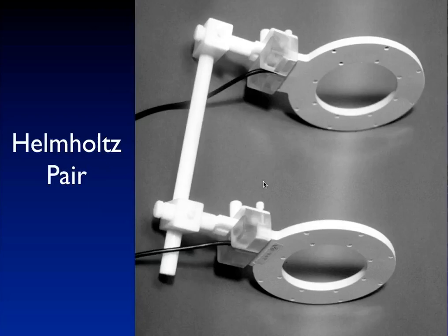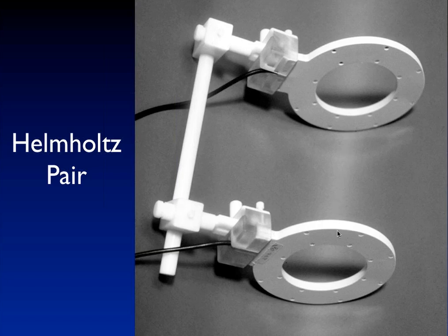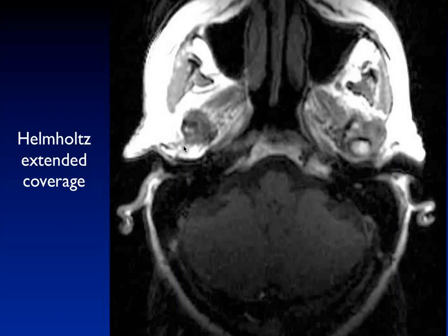A Helmholtz pair consists of two parallel loop coils. As described, you get more uniform signal intensity in the middle when they're spaced at about 1.3 times the radius of the coil. For many years this configuration was used for TMJ imaging to cover both joints simultaneously. Here's an example showing somewhat more uniform signal in the middle, though you still get brighter signal intensity adjacent to the two coils on either side of the head.